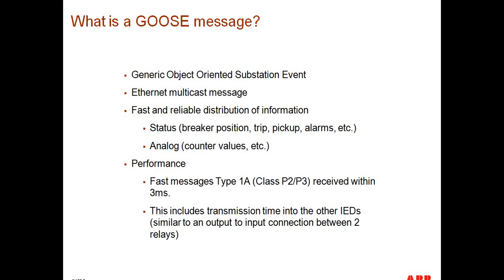Please clarify the name of the device between the CT, PT, and the relay. Well, that is an MU, a merging unit. So just to reiterate that point, from your current transformers and your voltage transformers, you're going to have leads. Those leads are wired onto the merging unit, and the merging unit will have a communications port that's connected to the Ethernet network that the other IEDs or protection relays are connected to, and then those relays can listen to the traffic generated by the merging unit.